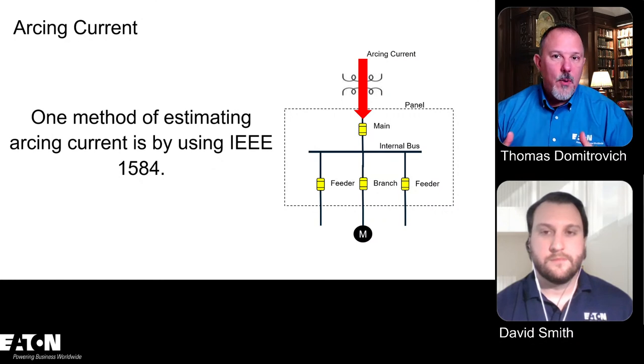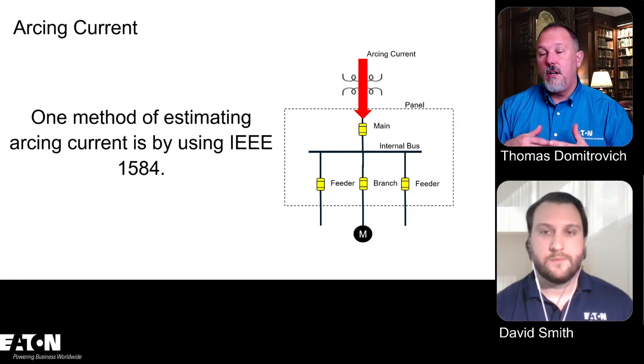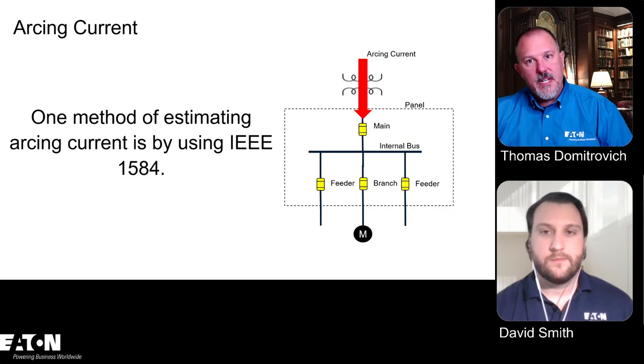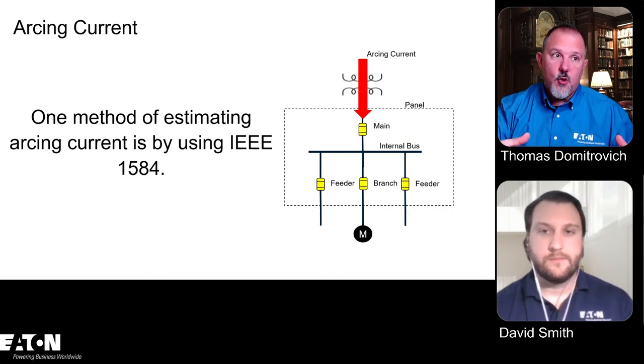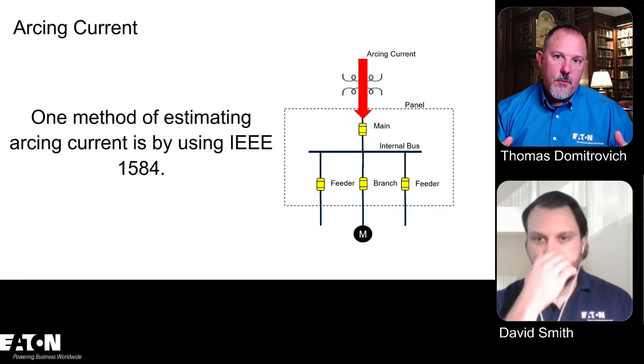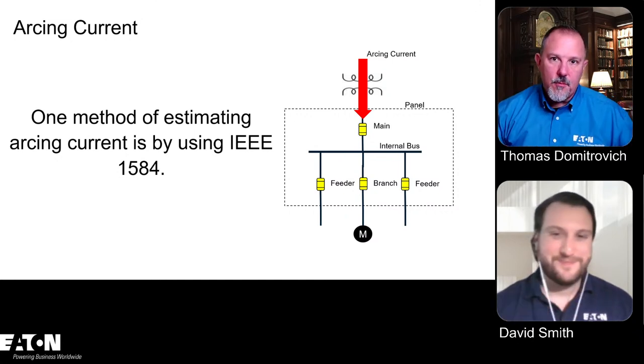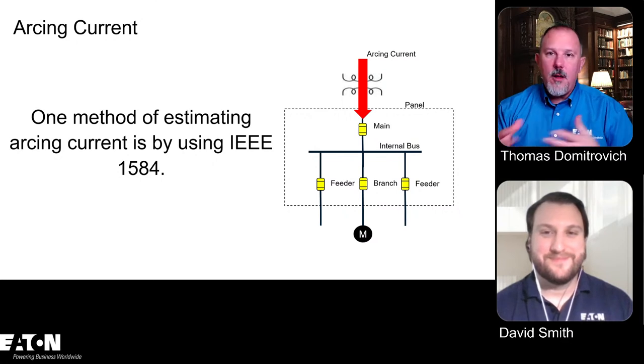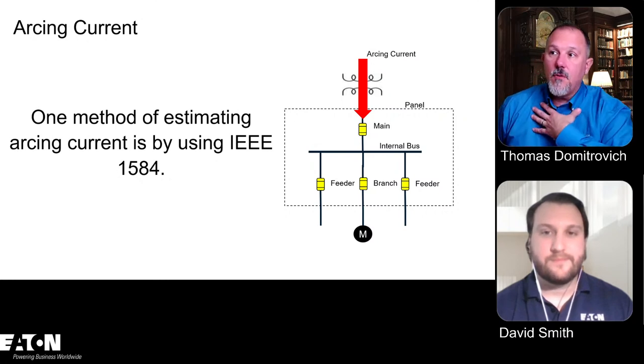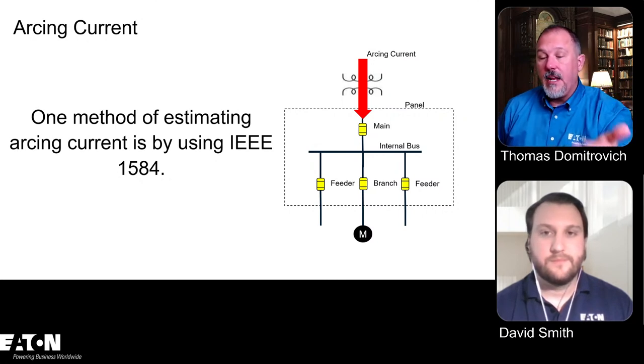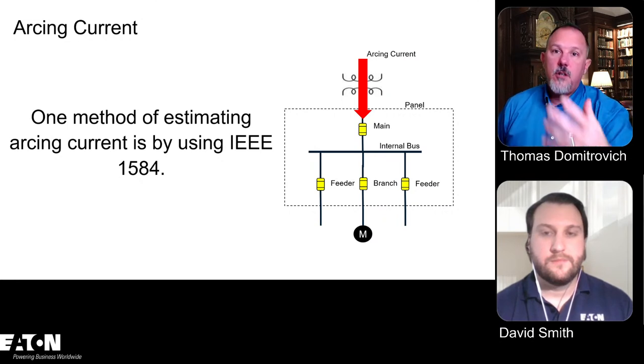But the damage to the equipment did not reflect 2-point-some calories. And I think that's because of a lot of different pieces of the puzzle. The clearing time of the overcurrent protective device was much faster. The spacings inside the equipment meant you didn't get that big plasma plume and have that arc go through and reduce it even more. So there were a lot of things, because our equipment is built a lot different than what we had in the lab. But I feel comfortable that even when you're calculating it in 1584, you're going to be conservative. So the electrical worker is not underdressed for the occasion.